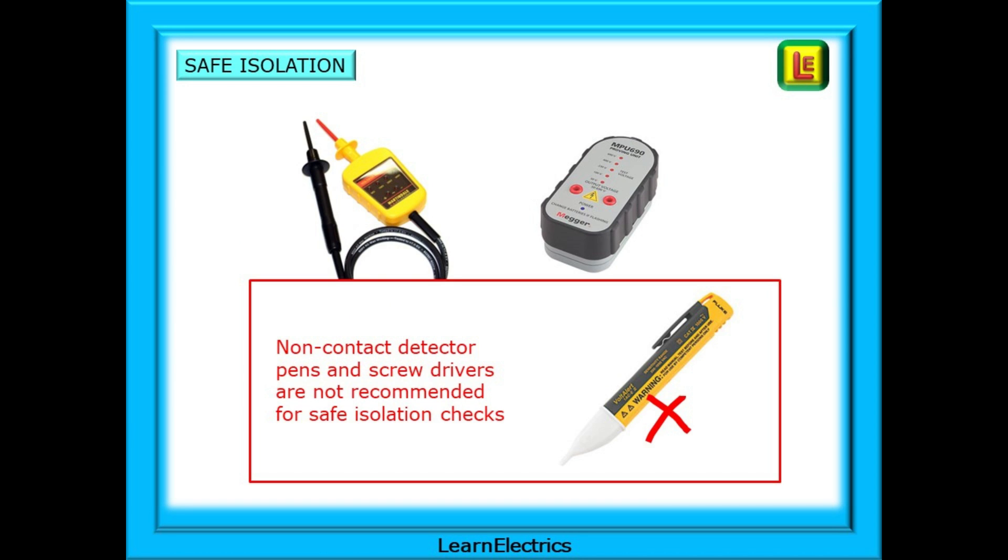Safe isolation, testing for dead, must be taken seriously. The wrong test equipment can put you or your colleagues in danger. One common device that many tradespeople think will prove a circuit is safe is the voltage detector pen. These non-contact detector pens and the voltage detector screwdrivers are not recommended for safe isolation checks. They will not always show when a voltage is present.